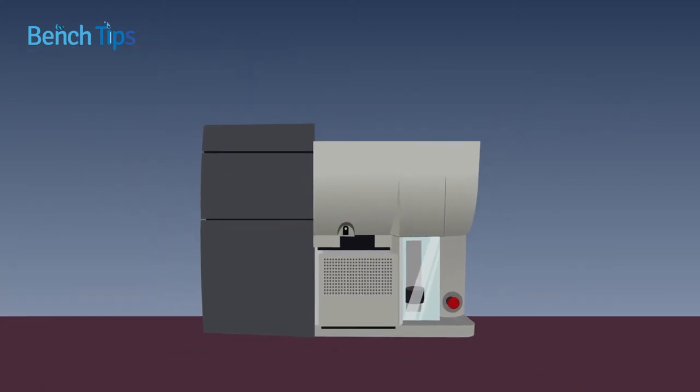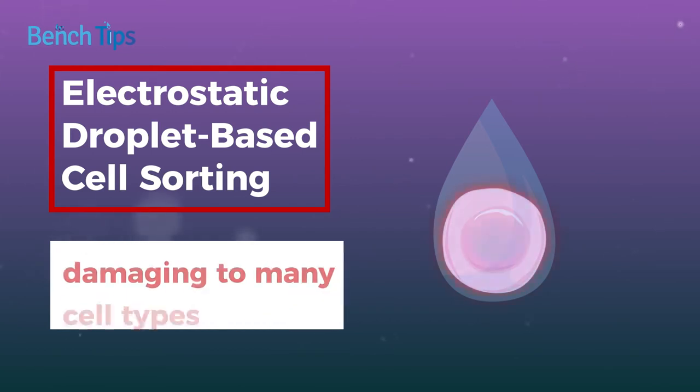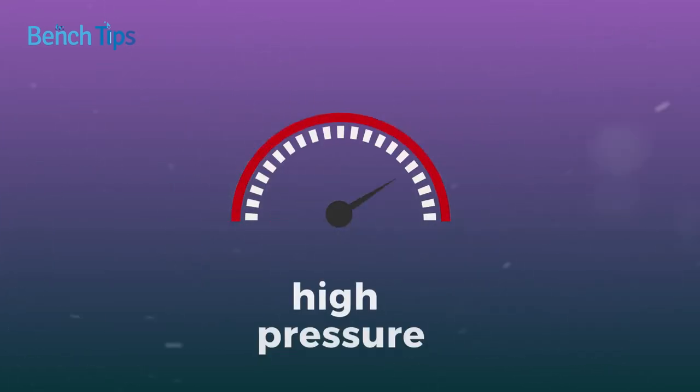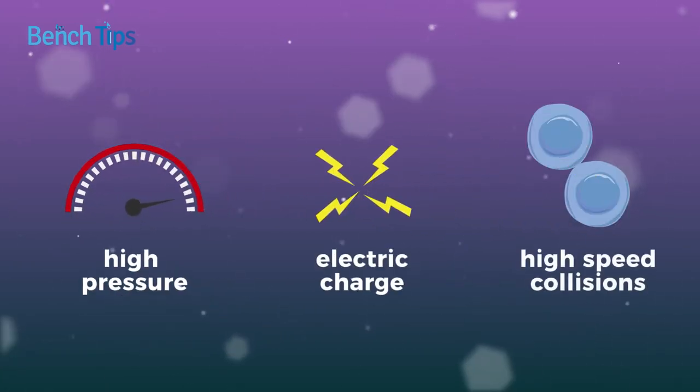Although both approaches offer distinct advantages, a major problem with electrostatic droplet-based cell sorting in general is that it can be damaging to many cell types. This is largely due to the combination of high pressure, electric charge, and the frequency at which high-speed collisions occur within a conventional cell sorter.